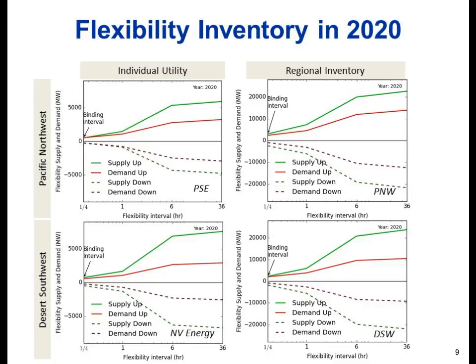And since the energy imbalance market wasn't being used in the historical record that we used, our parameters don't necessarily reflect what you might see, which is increasing ramps across interties going into the future because of that implementation of the energy imbalance market. So if we were to redo the same type of analysis in future years, if people are using the transmission more for faster ramping, we would see greater parameters, and that would then increase the flexibility supply that we'd see from the energy imbalance market. So that's one answer: we haven't really included it, but the parameters could be adjusted to reflect that.